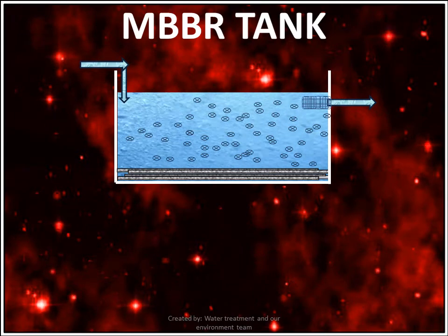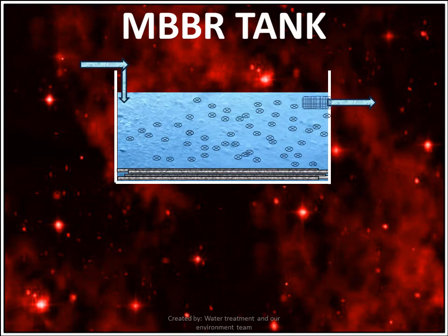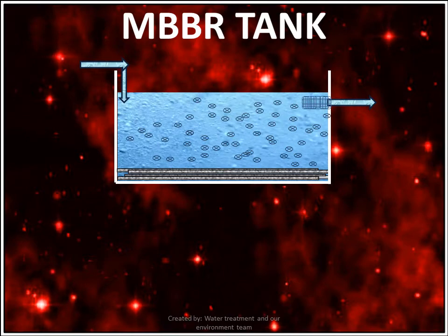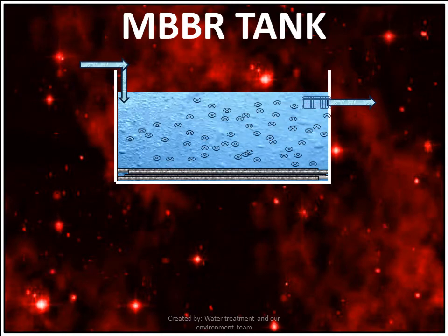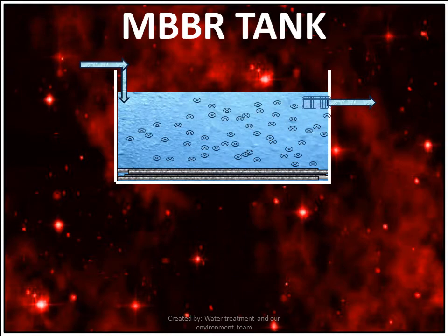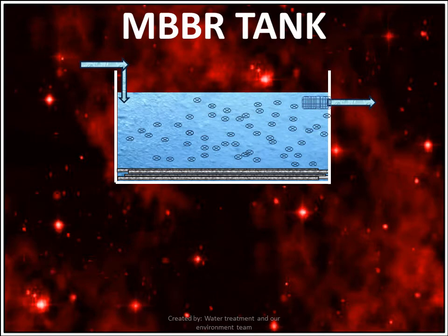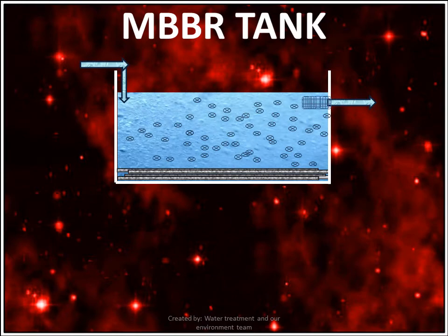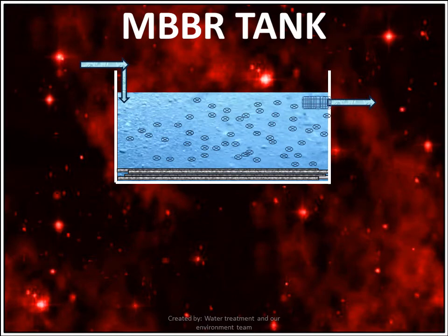The biofilm carriers are maintained in the reactor by the use of perforated plates at the tank outlet. Air agitation or mixers are applied in a manner to continuously circulate the packing. The packing may fill 20–50% of the tank volume. The specific surface area of packing is about 500 m² per meter cube of packing volume.